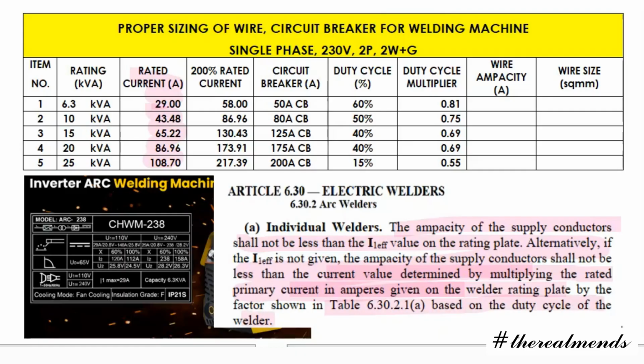So, that is what it says to get the wire ampacity. We multiply the rated primary current by the duty cycle multiplier: 0.81, 0.75, 0.69, 0.55 for their respective KVA ratings. Okay, from that we can arrive at the wire ampacity. So for the 6.3 KVA, we multiply the 0.81 by our rated primary current, which is 29. So we have a value of 23.49 amperes.